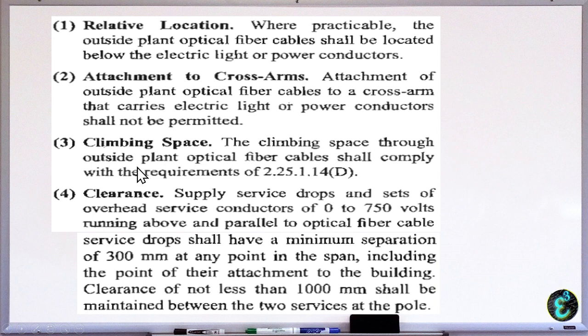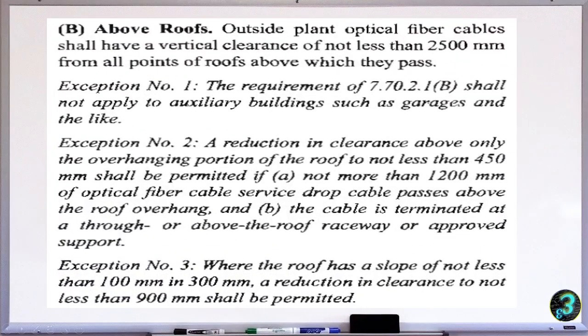Climbing space, so the climbing space to the outside plant conductor shall comply, no, with the requirement. So this requirement is the minimum clearance of the climbing space, which is katulad din kanina, yung 900 mm by 900 mm. So clearance, supply service drops, same doon sa ating communication circuits, so 300 mm at any point in span. Then a clearance of not less than 1,000 mm shall be maintained between two services at the pole. So above roofs, ganun pa rin, 2,500 mm ang kanyang clearance, no?